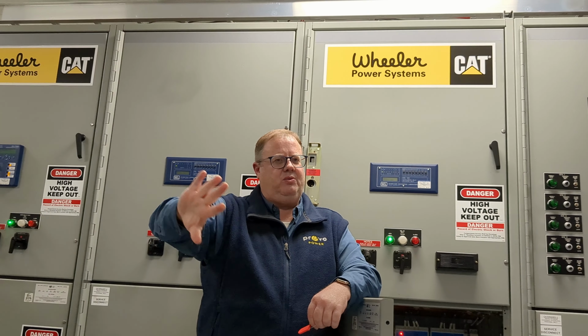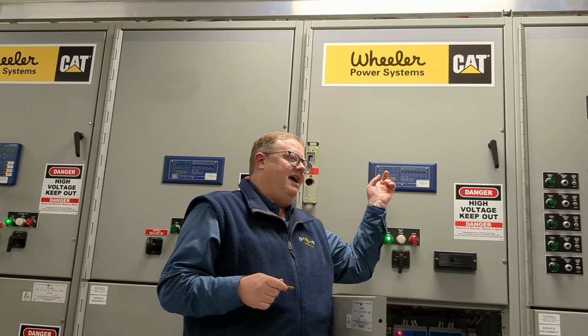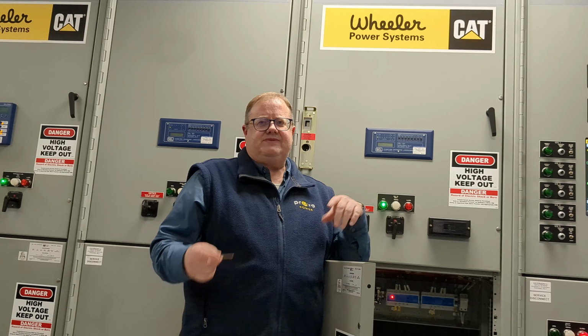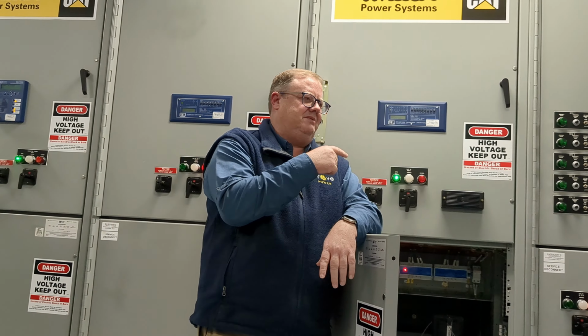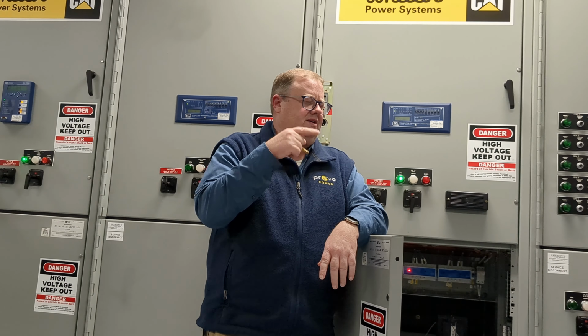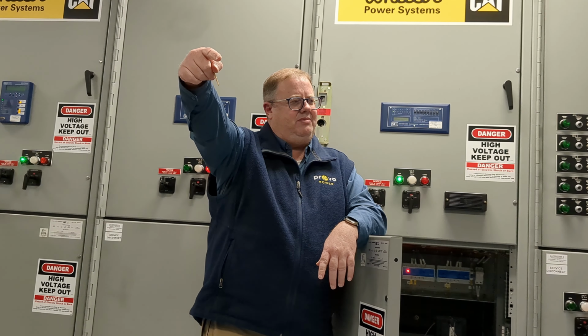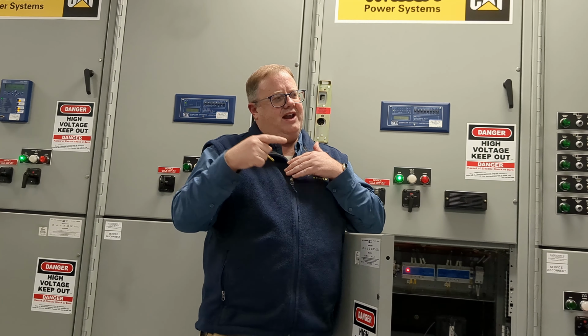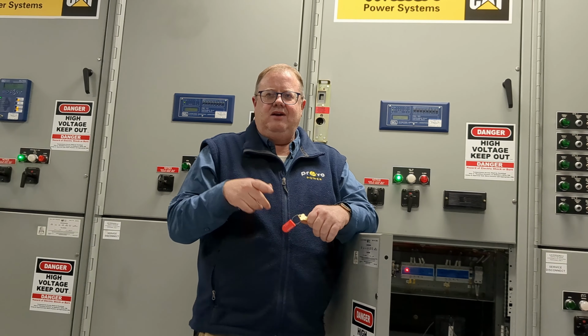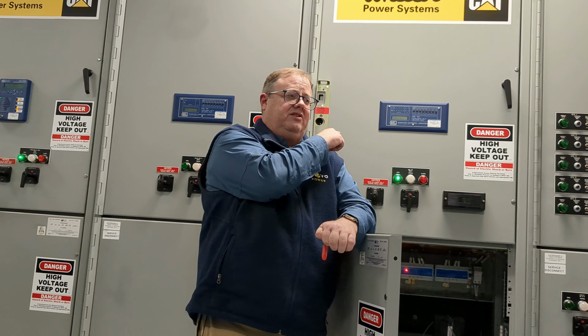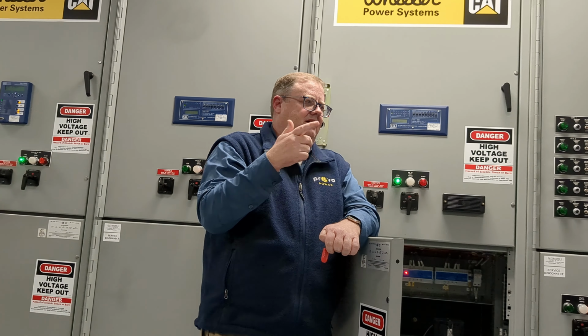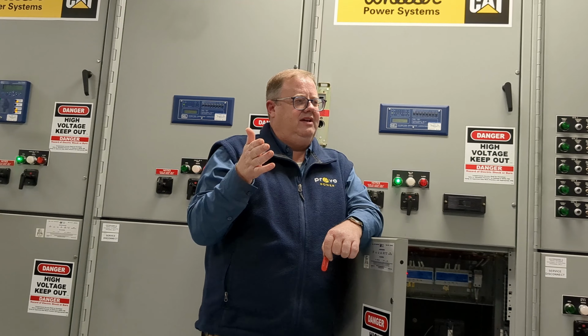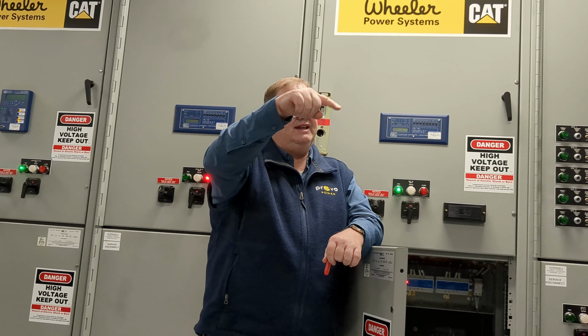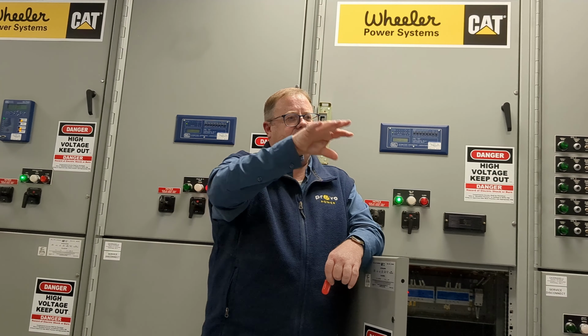So you hold it in, you say, I want the breaker to hold in on that fault this much time. Line. So if you model where the line is, you can tell where the fault is, right? If the fault current starts at the substation at about 10,000 amps, by the end of the line it might be about 3,000 amps. And if I know the impedance of the line, I can say, well, I read the fault current, it was 4,000 amps to ground. I know where the impedance is, I can look and see where the system fault is and predict where it is.